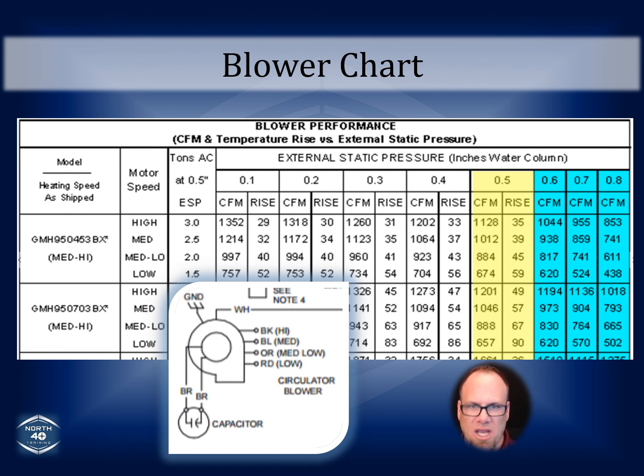But once you get up above the 90s, into that 95 degree plus range, all the little things that you didn't do correctly when you were out there servicing it or initially installing it, that's when those things show up. The extremities. Your furnace problems always show up at below freezing. Your air conditioning problems always show up in the 90s and above, because that's when all of those problems are exposed. When it's 90 some degrees in the Midwest, it's also really humid. At 85, sometimes people still have their windows open and you get a nice breeze across the house. But at 95 degrees and humidity added into that mix, it feels like it's into the hundreds.